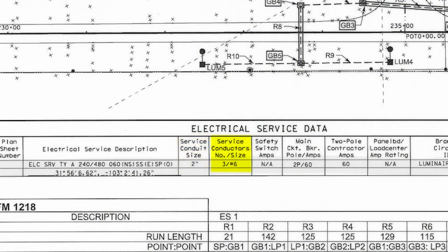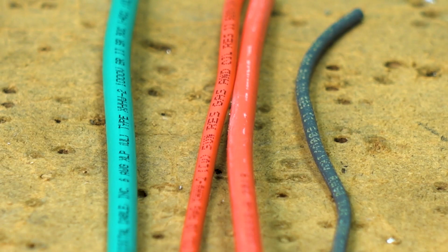The specified size of service conductors in the plans, either underground or overhead, can be determined from the service data sheet. The size of the installed conductors can be determined by locating the AWG size printed in small letters on the conductor insulation. Next, we will inspect the utility company's electric meter.